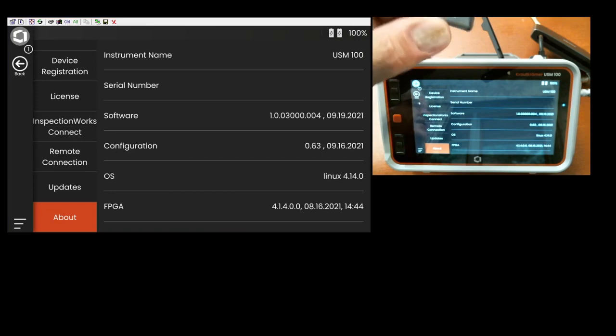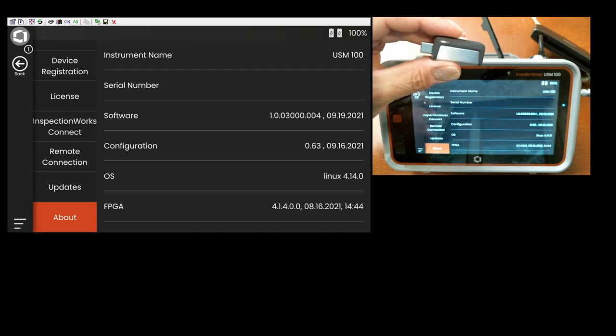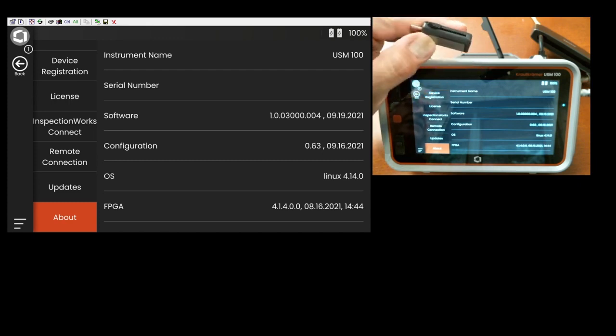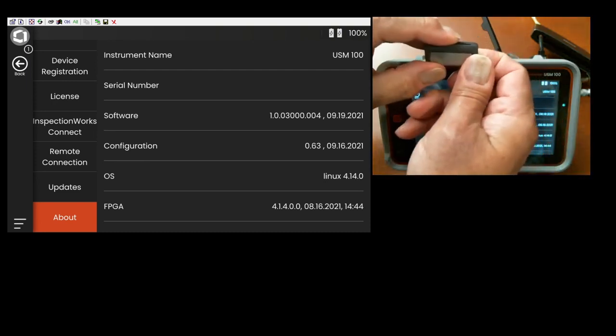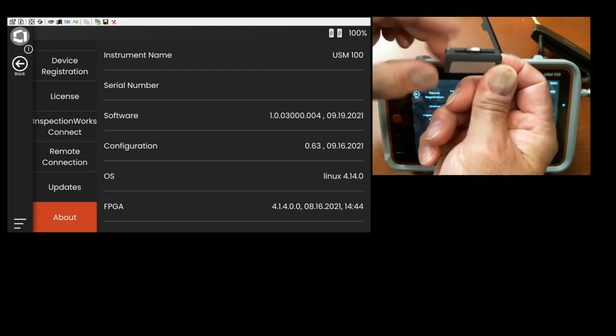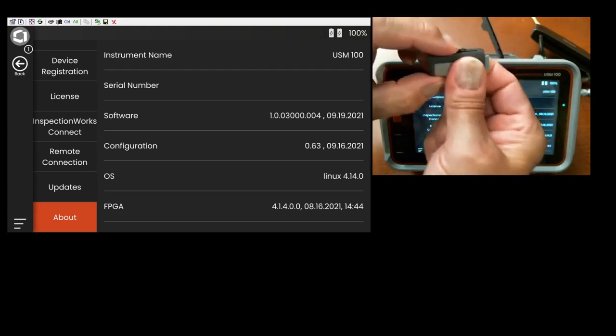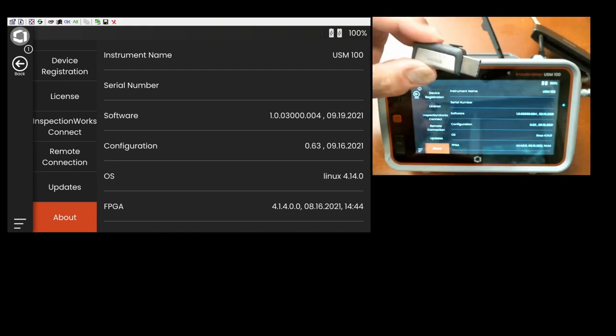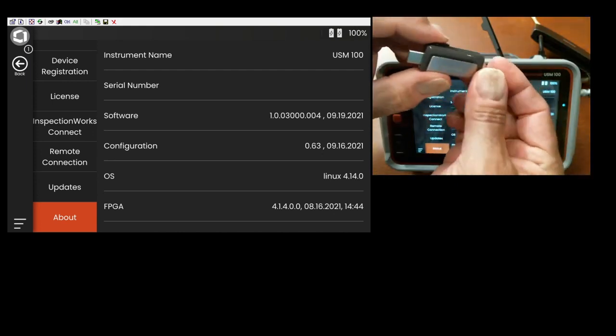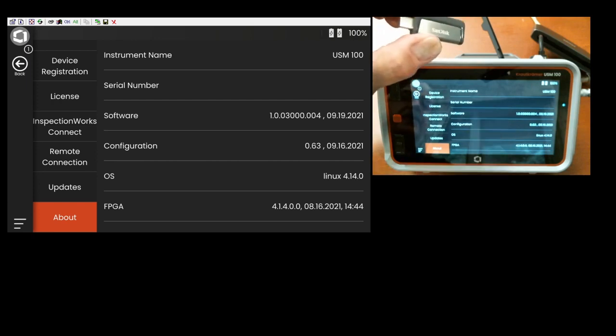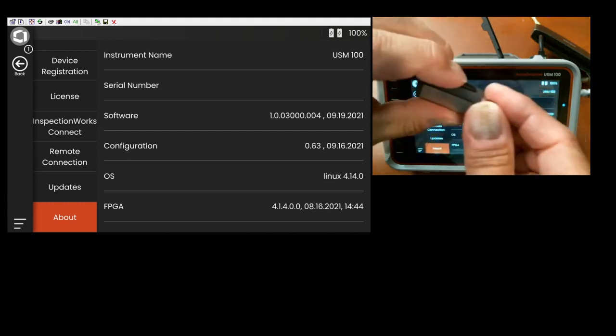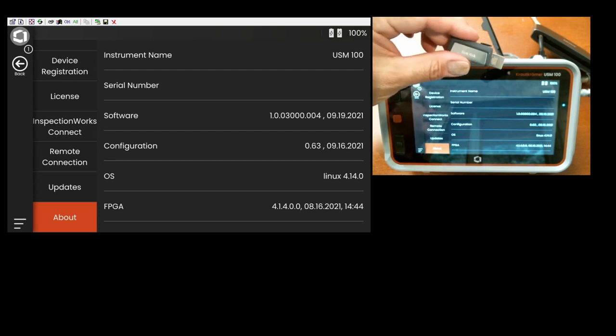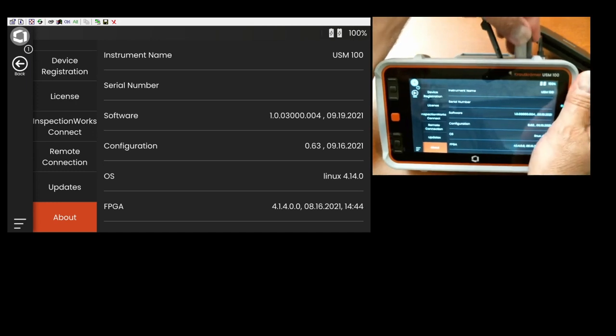So switching back to our instrument now. I'm using the USB stick that comes with the instrument. This USB stick has a little slider on the side. So the slider in the center, the USB ports are not exposed at all. Slid one way and latched, you get the traditional USB style connector. Push down, pull it the other direction. There's a USB-C style connector. You can use either one of those on the instrument. On my instrument right now, I have my docking station plugged into the USB-C. So we're going to use the older style USB connector. We'll go ahead and insert that into the instrument.